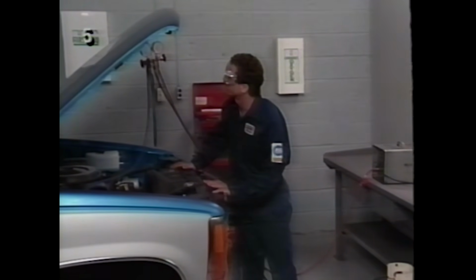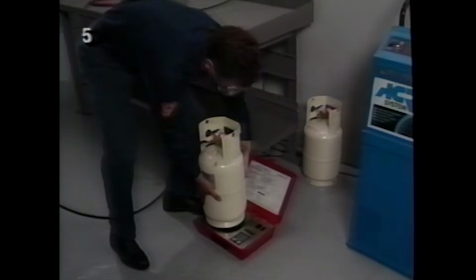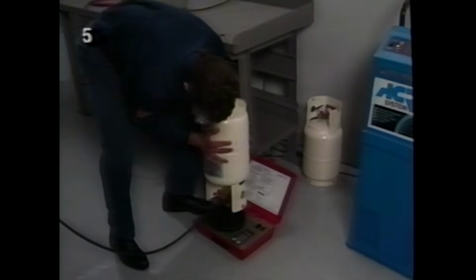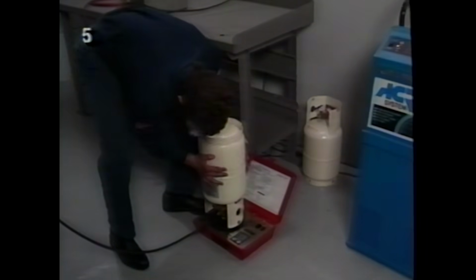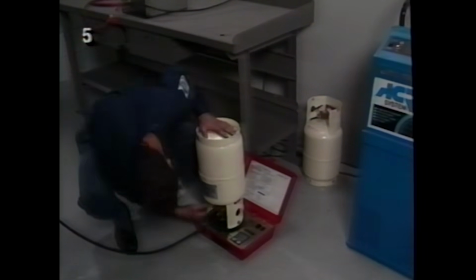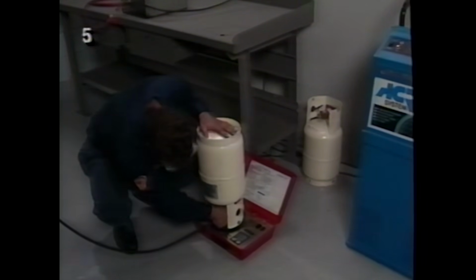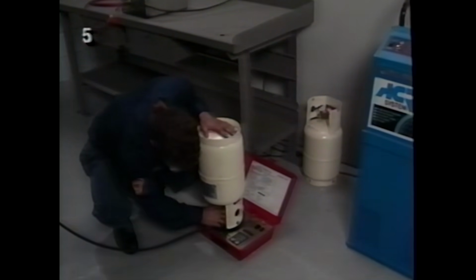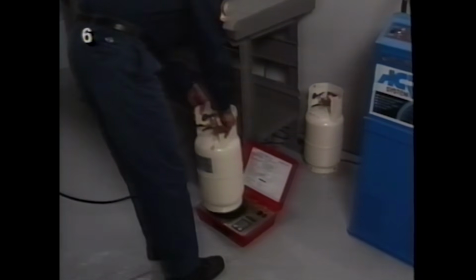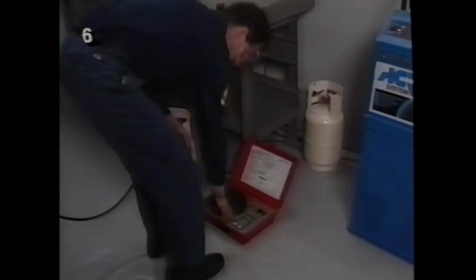If the system holds vacuum, go ahead and disconnect the vacuum hose at the gauge. If it doesn't hold vacuum, add 1/2 pound of R12 and leak check the system. If you find a leak, discharge the system back into the ACR3 recovery station, repair the leak, and repeat the evacuation procedure. Finally, to recharge the system, remember, it must be completely evacuated first.